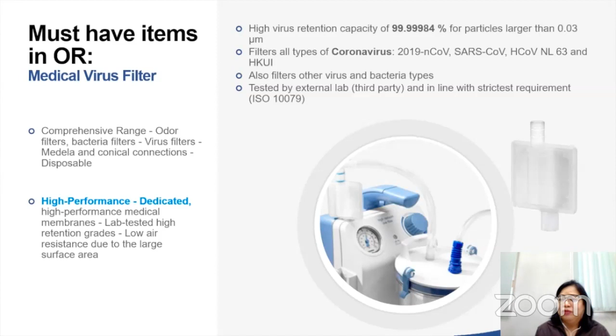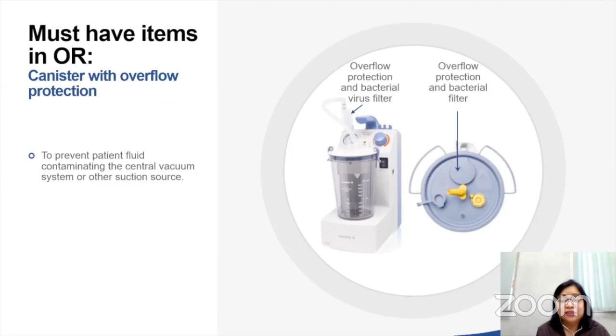Also, the canisters, the ones that contain your wastes, your washings, the blood, they should have overflow protection. So they should not be freely flowing so that it just overflows and spreads everything. And this overflow protection on top has to have filters so that the viruses can be trapped in these filters and not spread. They prevent the fluid from contaminating the central vacuum system if you do have a piped-in vacuum system or the other suction sources. With regards to surgical fluids, it's very important that the fluids don't spill, and I've seen it happen so many times.